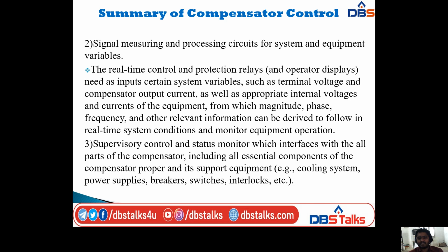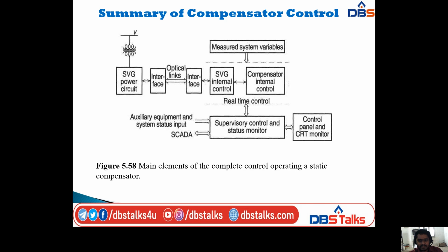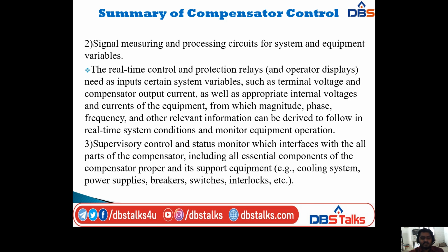And the third one is supervisory control. The real-time control is given to the supervisory control and status monitor, which interfaces with all parts of the compensator, including all essential components of the compensator proper and its support equipment, that is cooling system, power supplies, breakers, switches, interlocks, etc. All the components are included here.